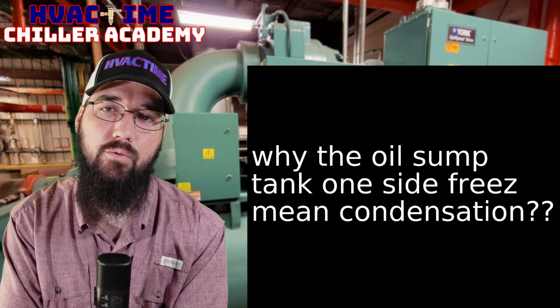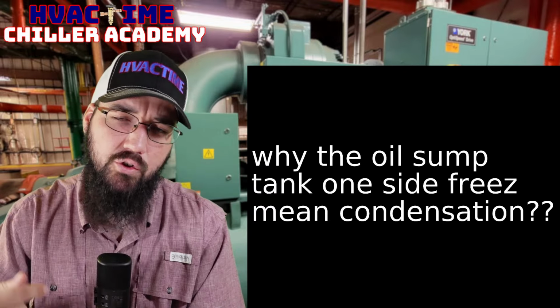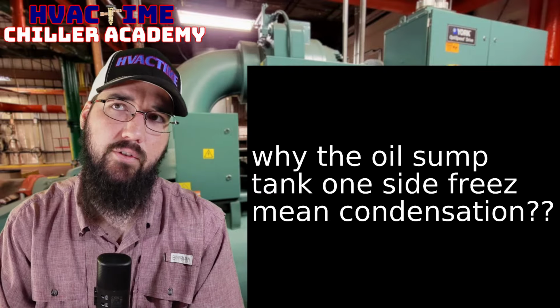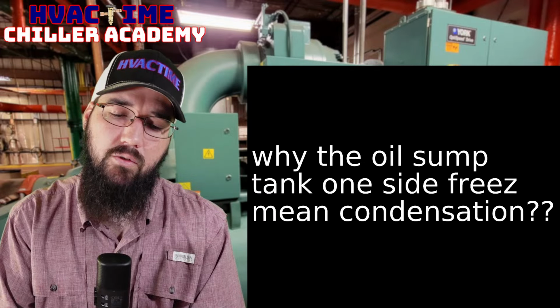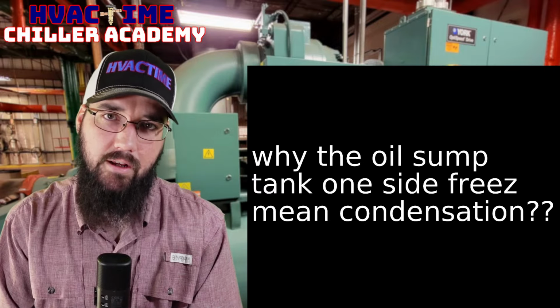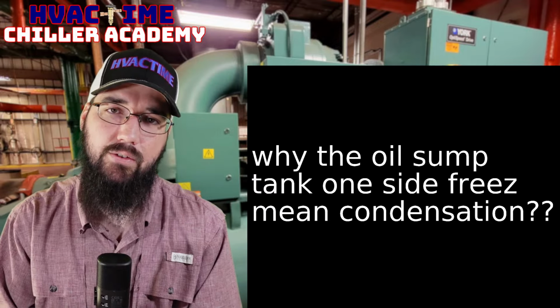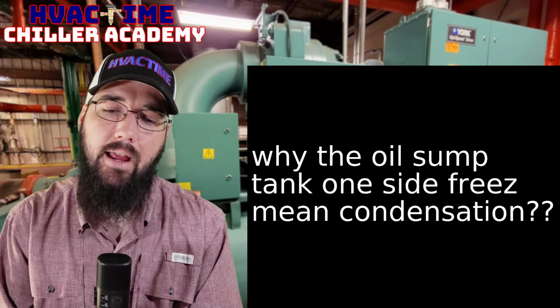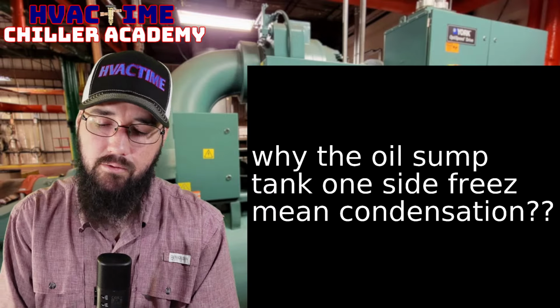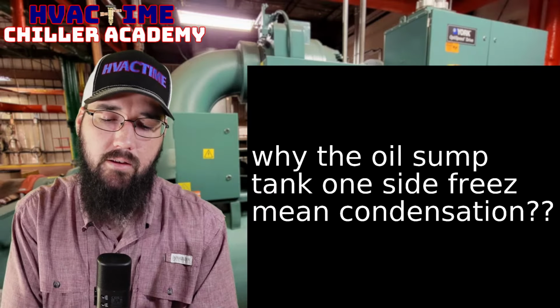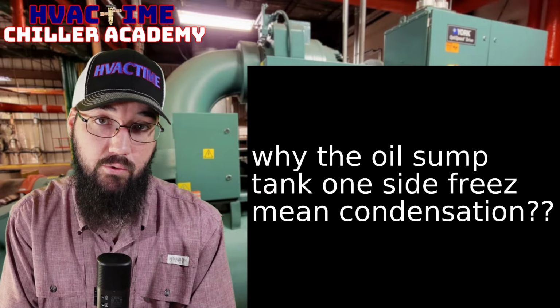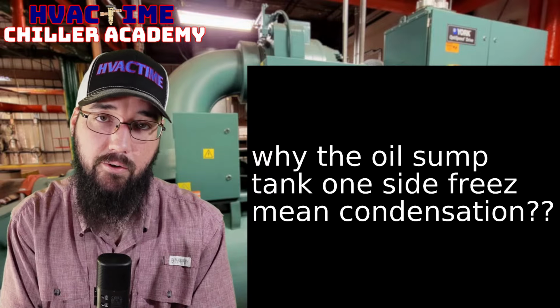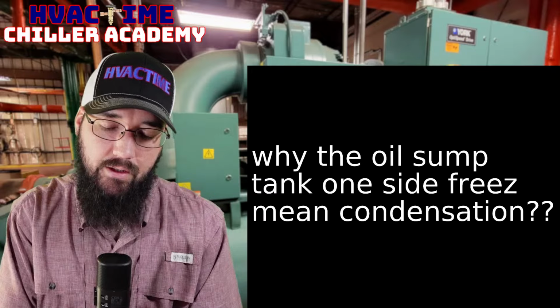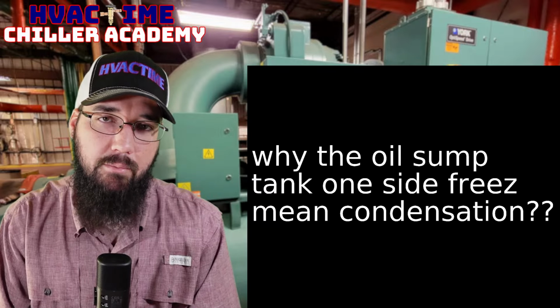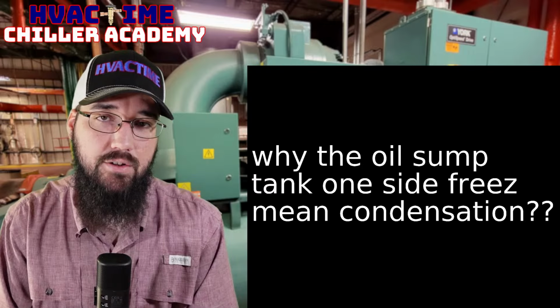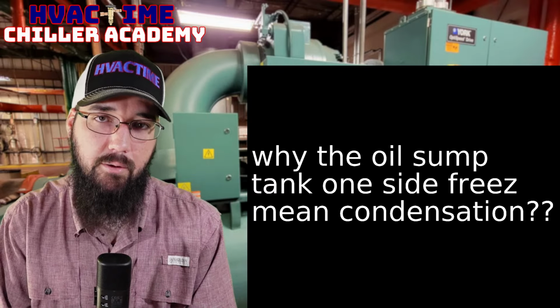So if you didn't know, on the Trane CVs, you're supposed to field set the eductor flow from the evaporator. At the evaporator where the eductor line or the oil return line connects, there is a service valve. And it's so common, people just don't know. I'm guilty of this too, by the way. I didn't know in the beginning. It's something I learned later. That valve is not meant to be opened all the way. It is an isolation valve, but it's not meant to be opened fully coming off of the evaporator.